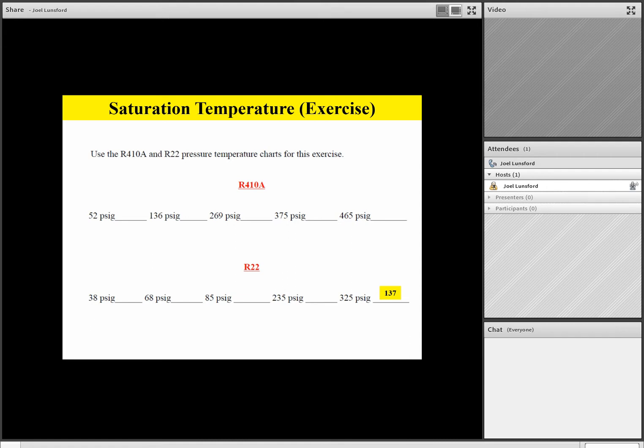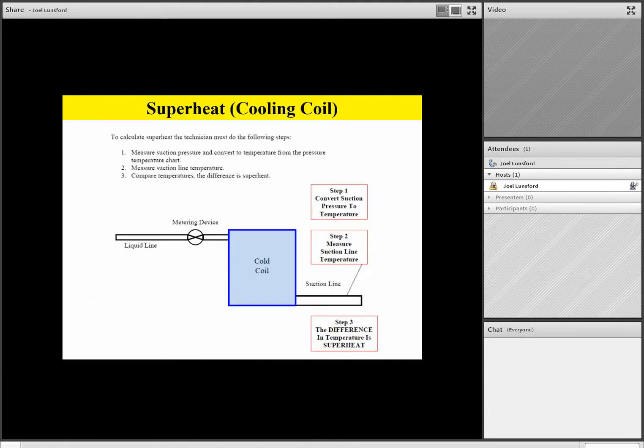So this time, let's talk about superheat and the cooling coil. Now remember, team, the cooling coil can be the indoor coil in the cooling mode of operation on a heat pump, but it can also be the outdoor coil in the heating mode of operation. So one thing we always need to keep in perspective is that superheat always applies to the cooling coil.